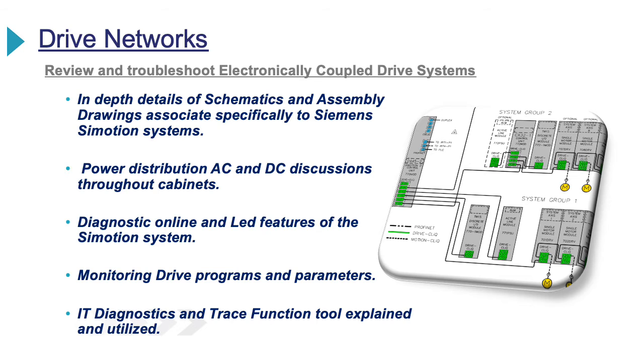The drive networks. Drive systems are not mechanically connected, but electronically coupled through software and some intricate networking. We will cover the in-depth details with the schematics and assembly drawings of what the networks are. Students will learn how these networks can be verified, such as going online with the software topology and making sure that they are connected properly for drawing. We will talk about the DC bus links, the diagnostic features built into the drives, and how to monitor them with trace functions that can help troubleshooting as the press is running.